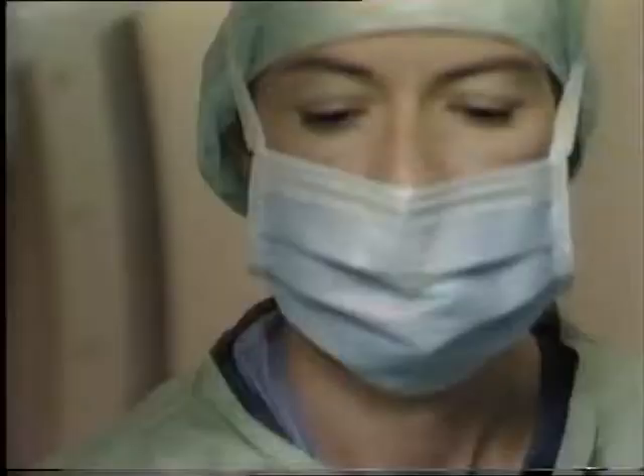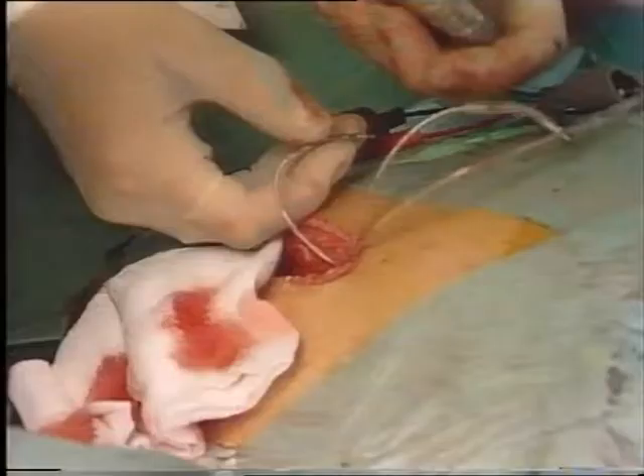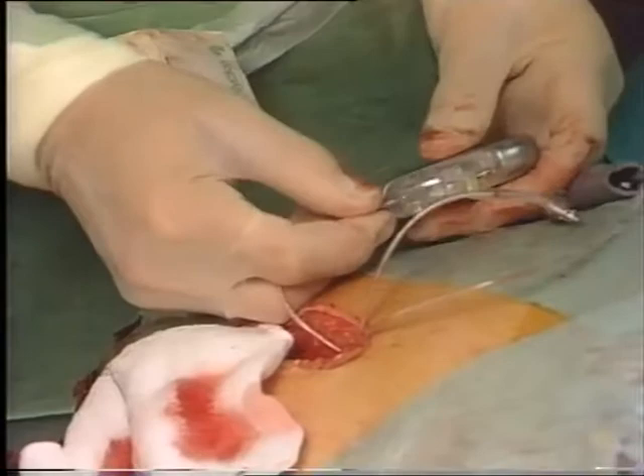But how does it work? The Metrix Atrial Defibrillator is a device which is implanted in the body. It recognizes atrial fibrillation, and when it recognizes it, it charges and then discharges to convert atrial fibrillation to sinus rhythm.